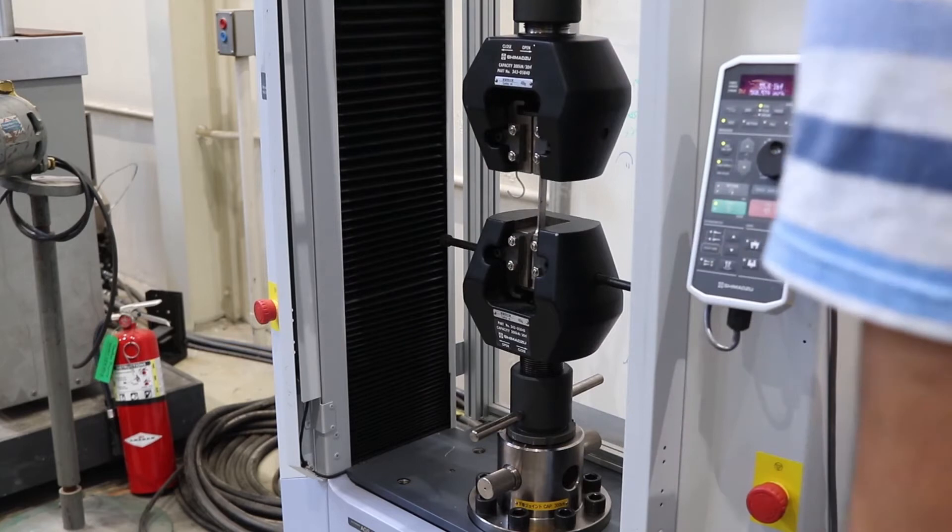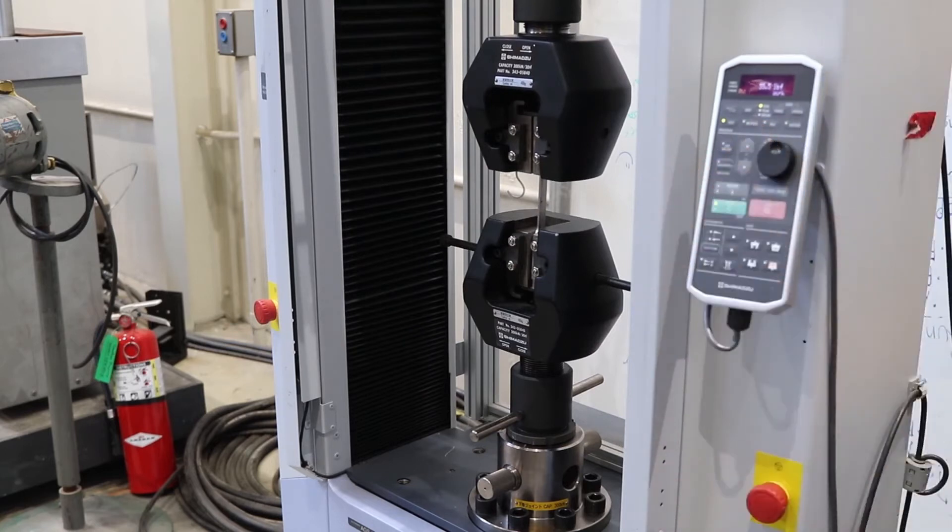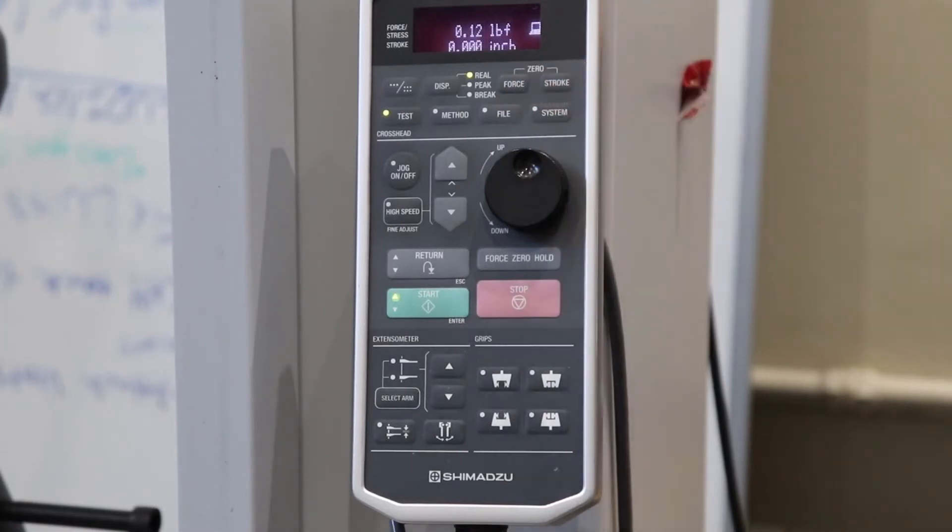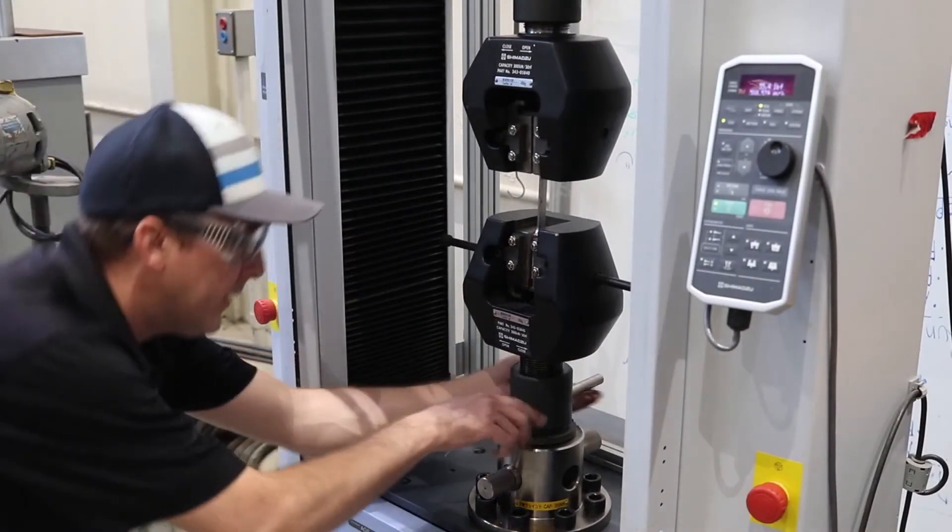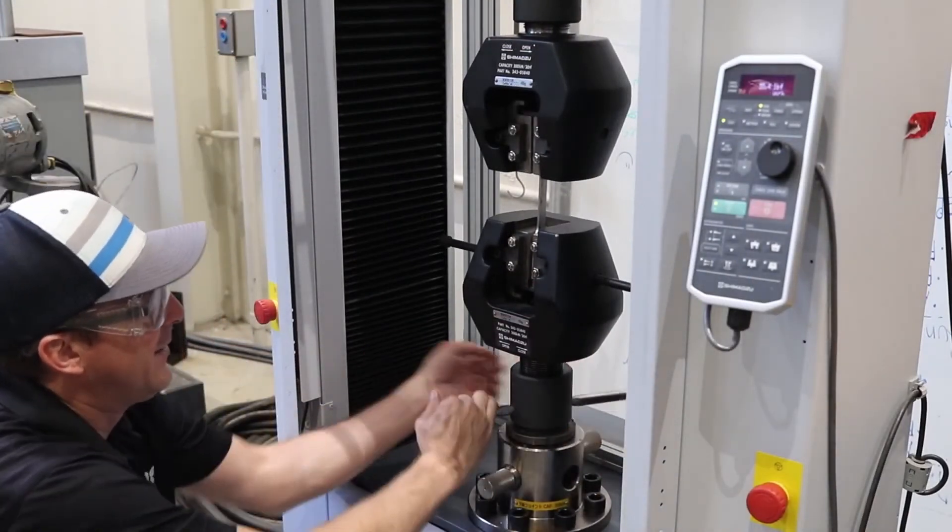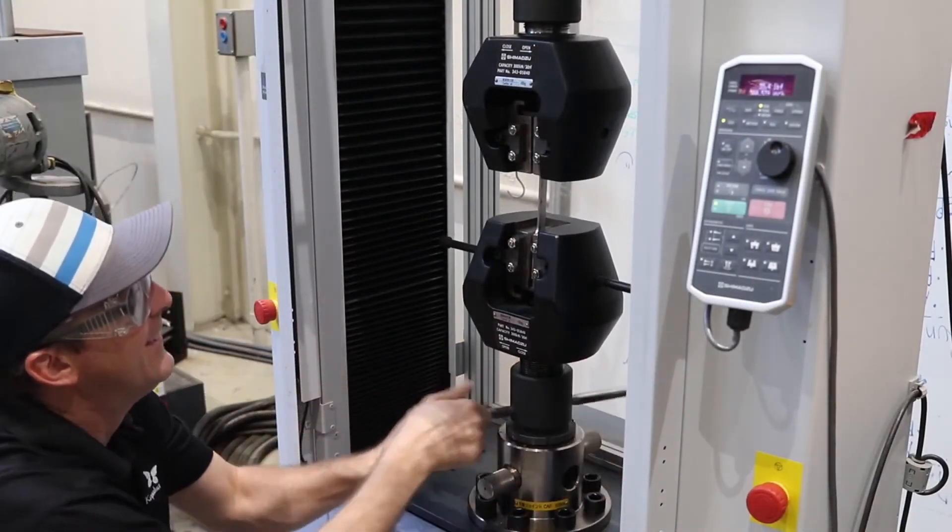After we are done jogging the head, we press the Jog On and Off and High Speed off. We now zero the machine on the control panel using the Force Zero and the Stroke Zero. This step is important to measure the preload. We now tighten the lower jaws, preloading the specimen.